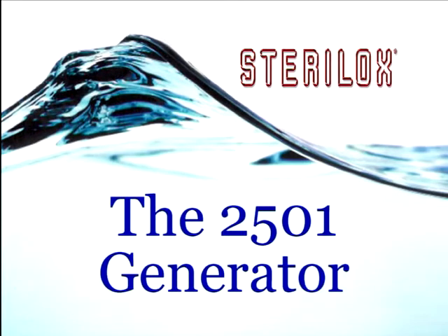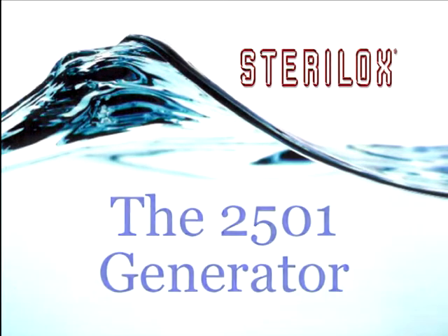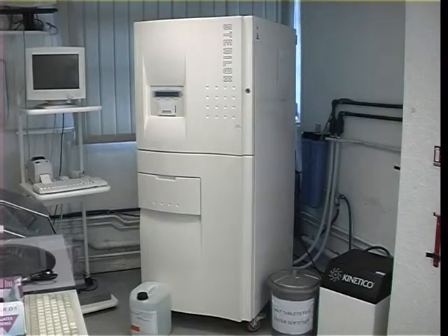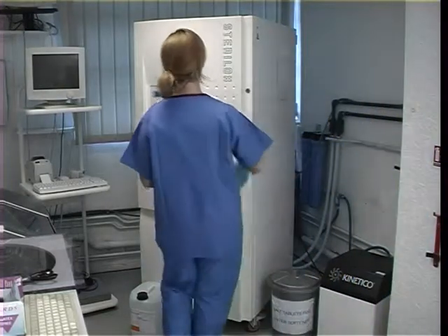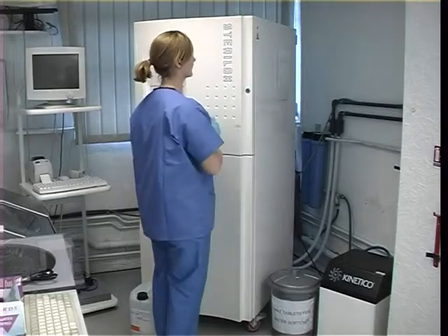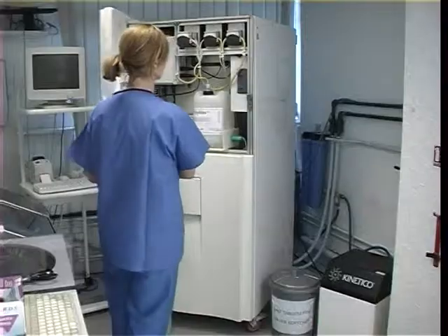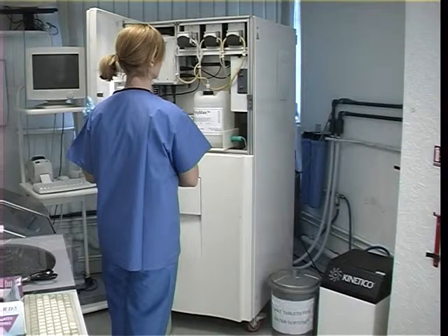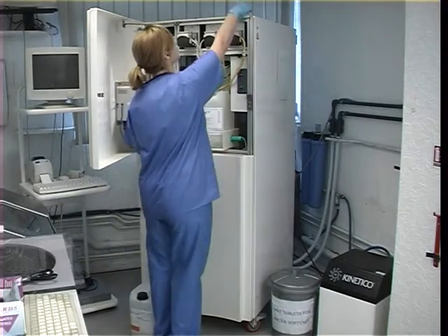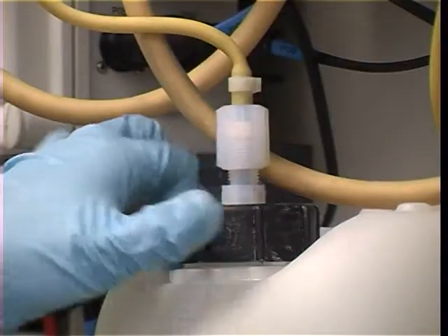The 2501 generator. The key for your 2501 generator should always be kept on the top of the machine at the right-hand side. Use the key to open the front panel. The Polymax container is inside this panel. This container holds the anti-corrosive liquid used to protect the internal parts of the generator.